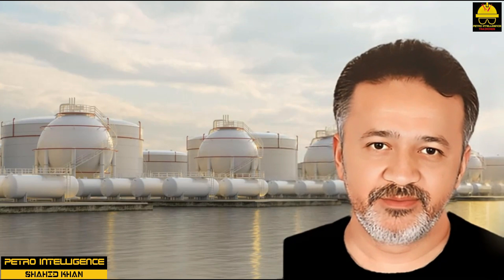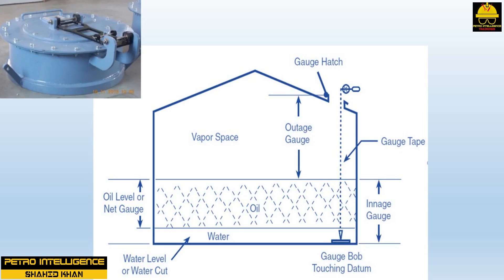Gauge hatches are provided in the roofs of atmospheric tanks to enable the contents to be measured. A secondary function of a gauge hatch is to provide some emergency pressure relief. Except when in use, gauge hatches should be kept closed to prevent loss of vapors, fire hazards, and entry of rainwater. Hatches should not be weighted or otherwise restricted from opening, as restricting them eliminates their function as a pressure relief device. The datum plate directly below the open hatch is used as a reference point when a technician is measuring liquid level with a gauge line.